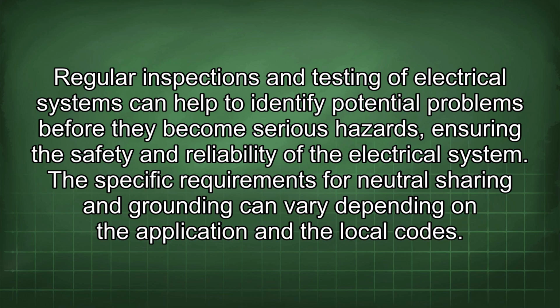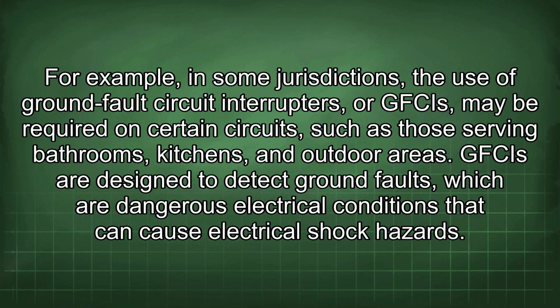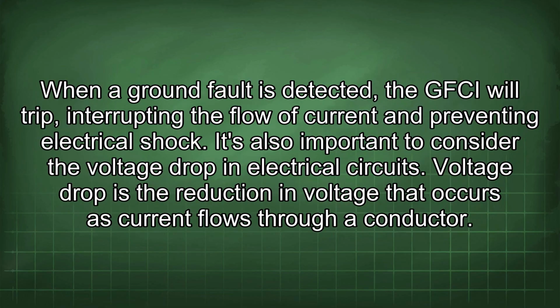The specific requirements for neutral sharing and grounding can vary depending on the application and the local codes. For example, in some jurisdictions, the use of ground fault circuit interrupters, or GFCIs, may be required on certain circuits, such as those serving bathrooms, kitchens, and outdoor areas. GFCIs are designed to detect ground faults, which are dangerous electrical conditions that can cause electrical shock hazards. When a ground fault is detected, the GFCI will trip, interrupting the flow of current and preventing electrical shock.